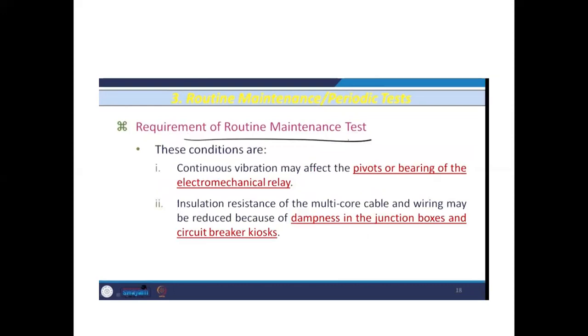Requirement of a routine maintenance test. These conditions are: continuous vibration may affect the pivot or bearing of the electromechanical relay. The pivots and the bearings should be working properly, and continuous vibration may affect these two components, so these should be periodically checked. Insulation resistance of the multi-core cable in wiring may be reduced because of dampness in the junction box and circuit breaker kiosks. So insulation resistance should be checked, because it may be reduced by dampness. This resistance should not be low in normal condition.